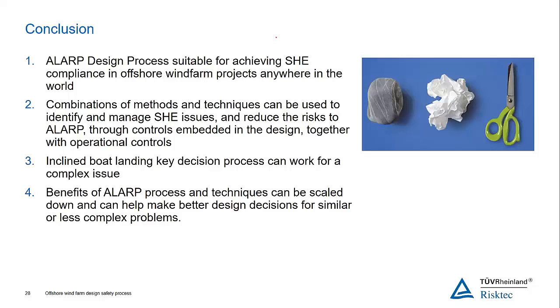Well, those are typically covered in DNV industry standards, which are typically what are applied in the UK anyway. If you talk about an offshore substation, they would specify the requirements for a secure access. So they would have a mariner's cage where you could get to a certain point, so that for life safety you can climb and seek shelter in the mariner's cage, but it's locked and you can't get to the equipment via that route. CCTV as well would be another way of detecting intrusion, and those sorts of measures would be encapsulated within the standards.